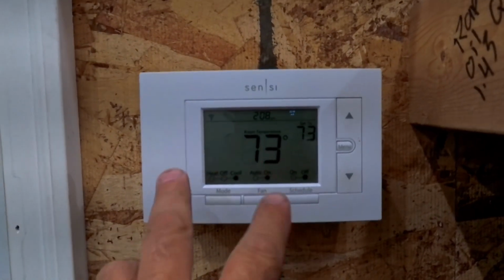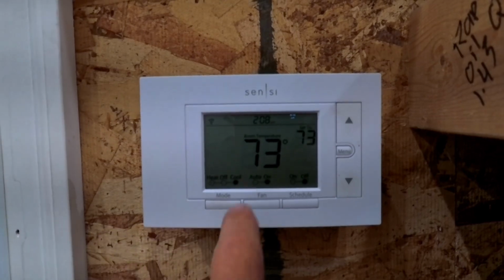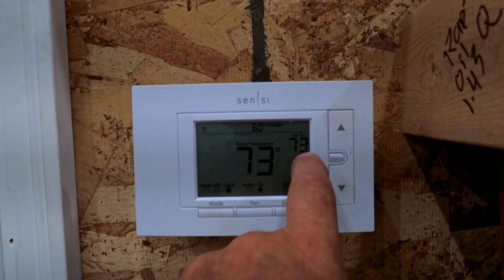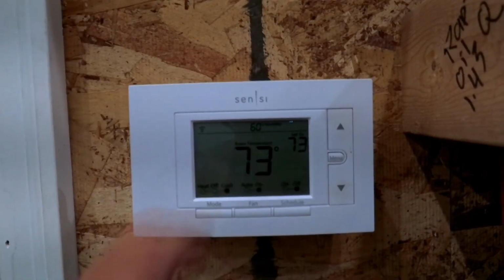Second thing, it's lit up, everything seems to be working. The set temperature is obviously not being satisfied, and it's hot in the house. So now that we verified the thermostat is in fact calling for cooling and the system's not working, we need to go through and figure out who's working and who's not working. Now the thermostat is going to tell the furnace to turn the fan on, and it's also going to tell the outdoor unit to turn on also. So it's going to be doing 2 different tasks, and we need to figure out which one is actually working.